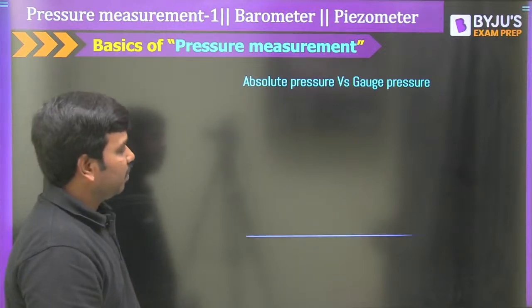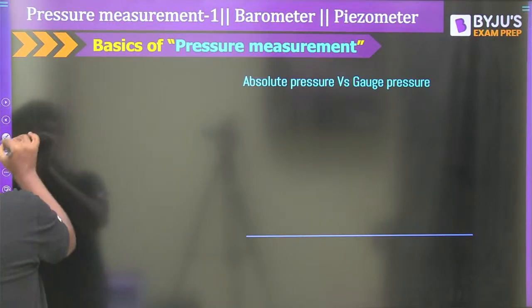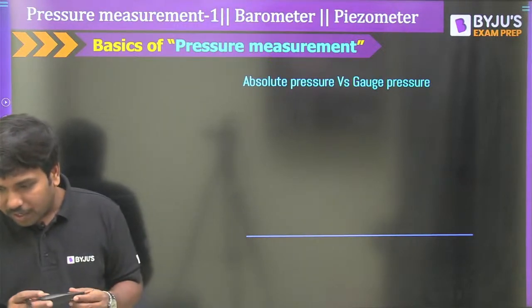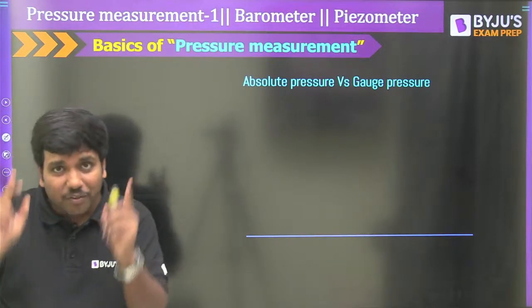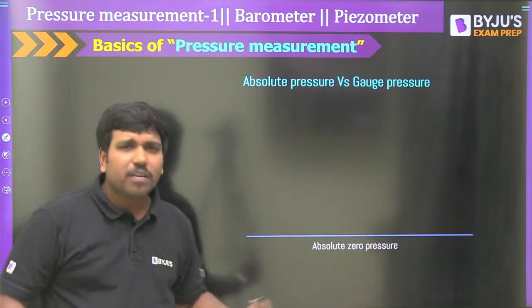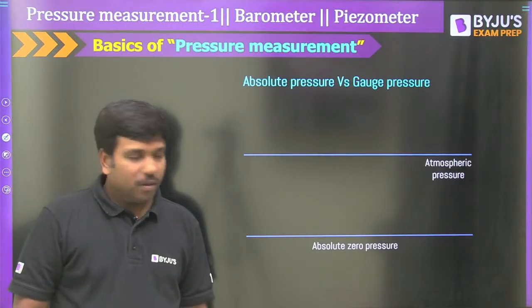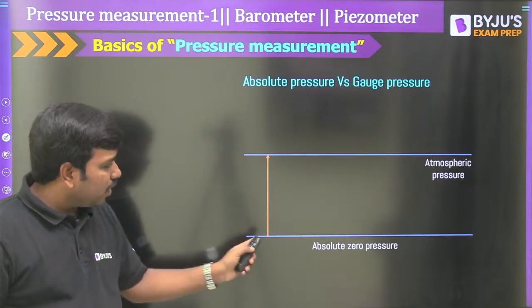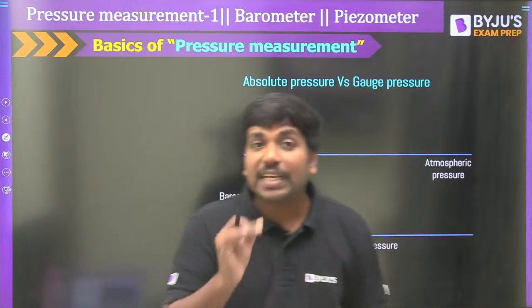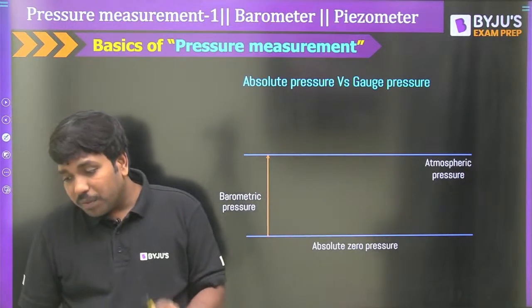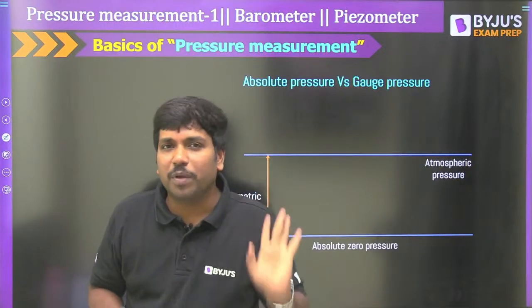Let me explain the absolute pressure versus gauge pressure chart. Consider zero as absolute zero pressure. Atmospheric pressure measured by a barometer is called barometric pressure — barometric pressure is simply atmospheric pressure. If gauge pressure is positive and added to atmospheric pressure, the absolute pressure will be more than atmospheric pressure. If gauge pressure is negative — vacuum — absolute pressure will be less than atmospheric.